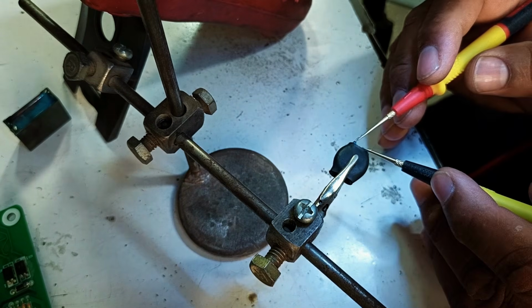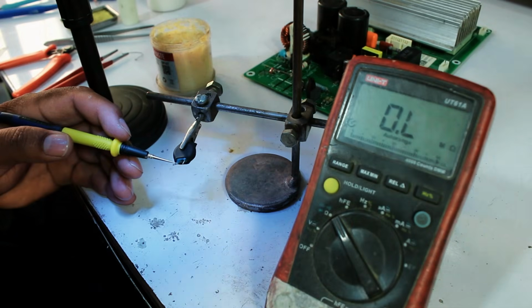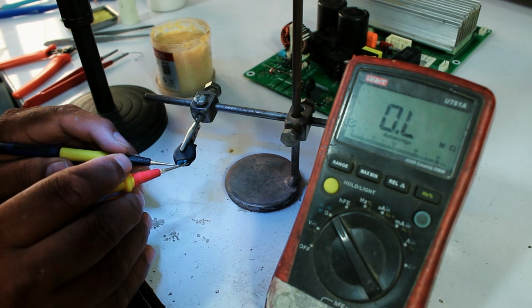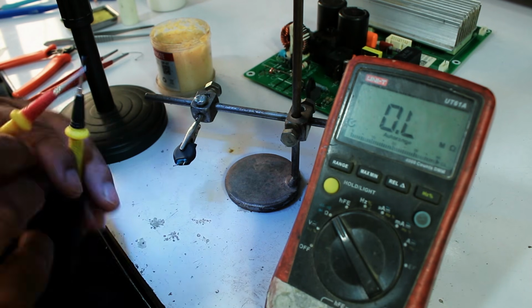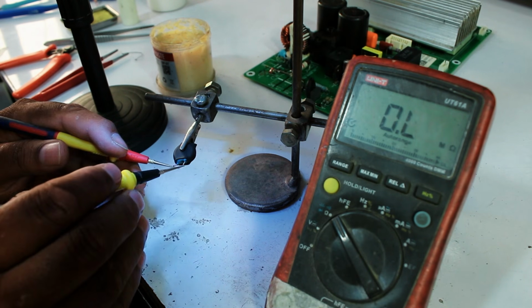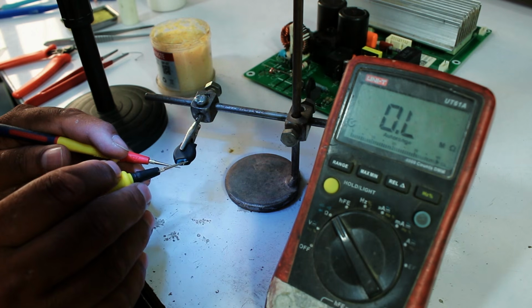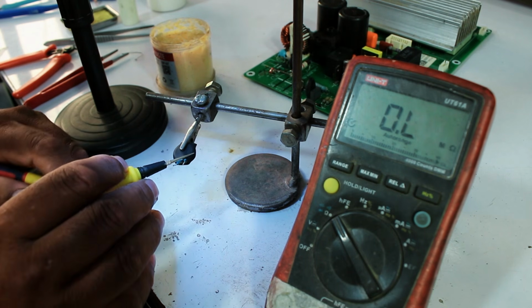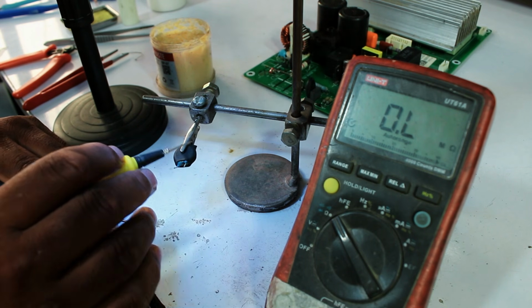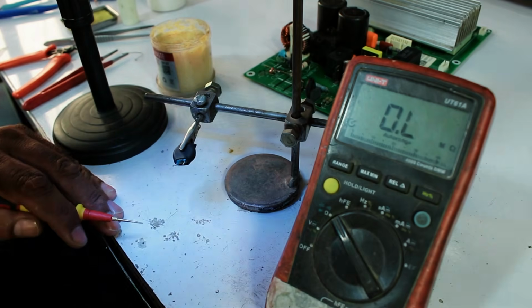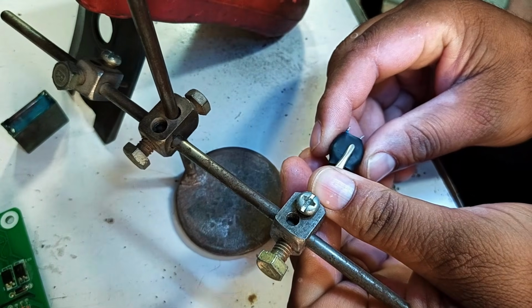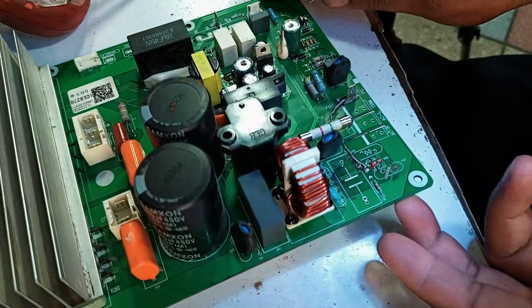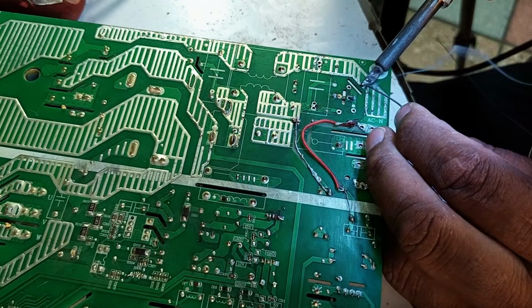Now let's check the second ZNR. When I connect the probes to this one, look, it is not showing any resistance value here. This means there is a chance that this one may be okay. Sometimes, even if a ZNR looks okay when checked with a multimeter, it can still cause the breaker to trip in some cases. But right now, this one looks fine to me, so we will install this ZNR back in its place.